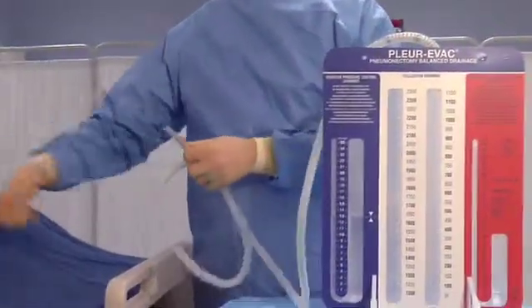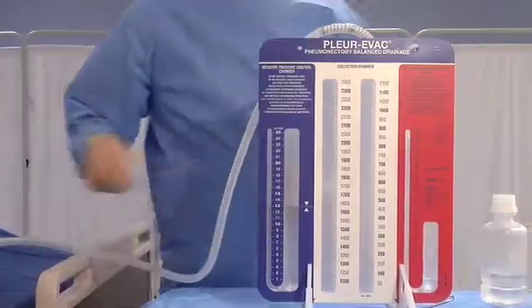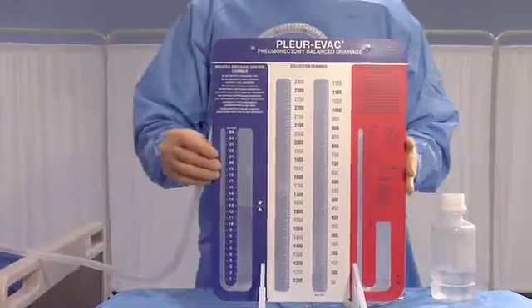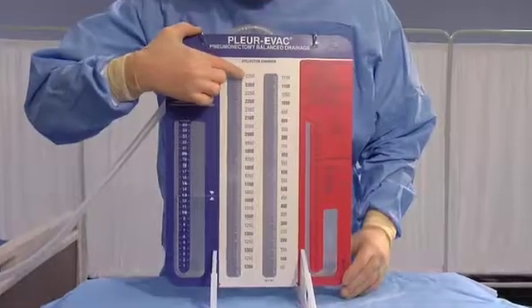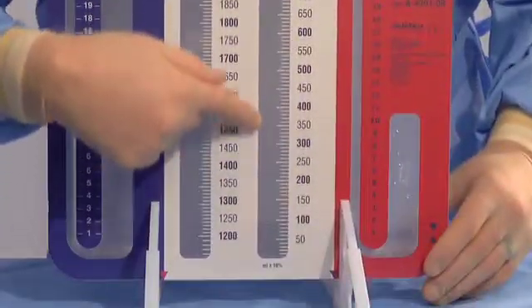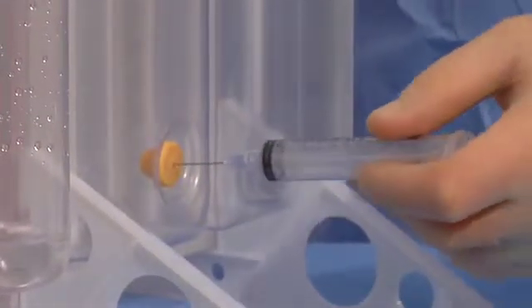Remove and discard the protective cap on the Pleur-Evac patient tube connector. Connect the patient drainage tube to the patient's thoracic catheter. The patient collection chamber has a total capacity of 2,350 cc's and is divided into two compartments, each calibrated in 10 cc increments. A self-sealing diaphragm is provided in the back of the collection chamber. Use an 18-gauge needle or smaller, attached to a syringe, for withdrawing samples. Marking surfaces are provided on the front of the unit; use pencil or pen.